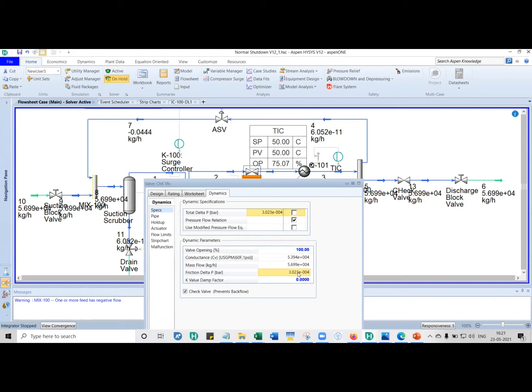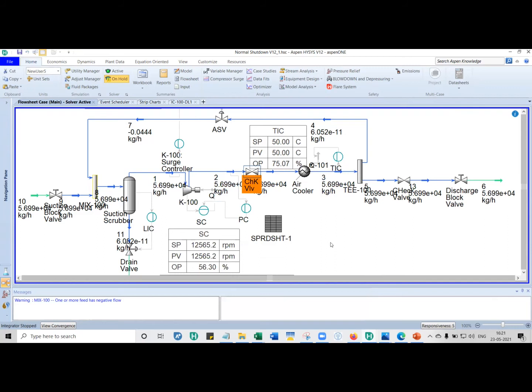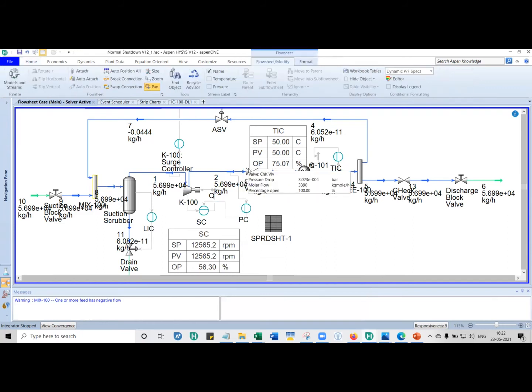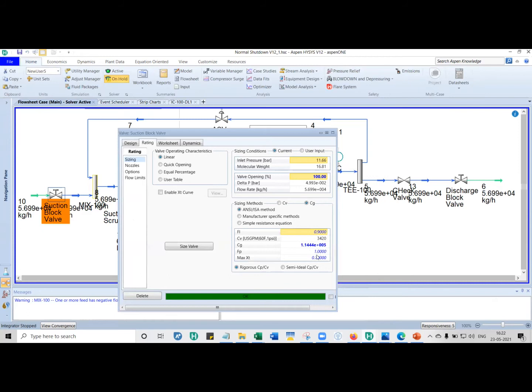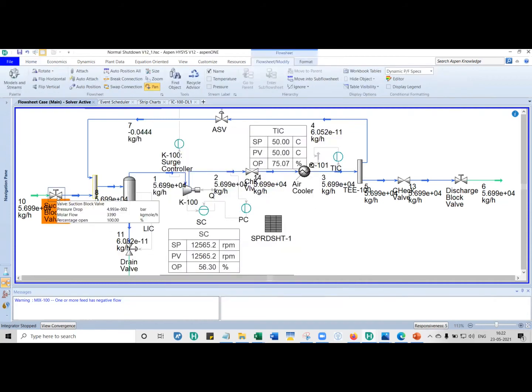In reality in the field there will be some pressure drop, but for simulation purposes we approximate it to almost no pressure loss. For both check valves and block valves, give a high CV value. Because if they are all full bore valves — you have a pipe and a valve, and if it is open, the valve opening is the same as the pipe opening — so you give a high CV to say there is hardly any pressure drop. Check valves and block valves you just approximate to almost no pressure drop.